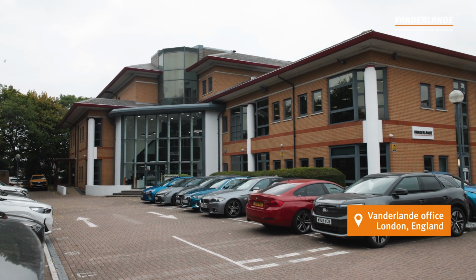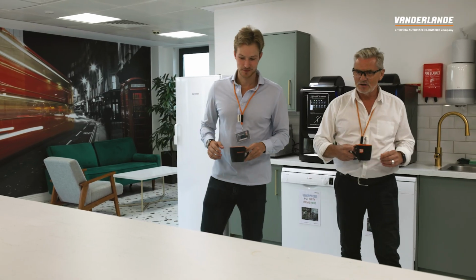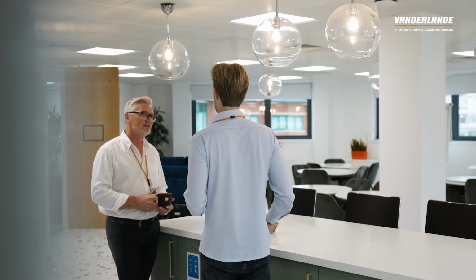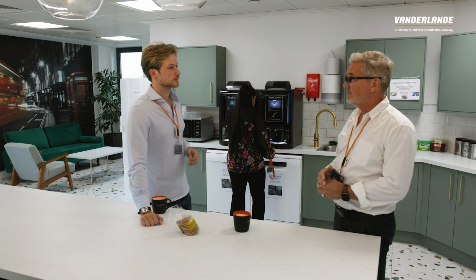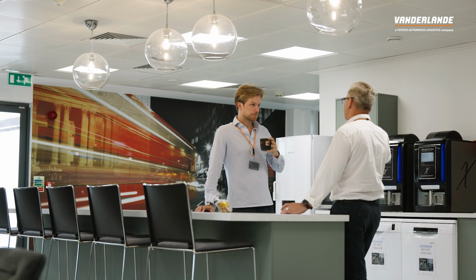Yeah, after all the online meetings, it's good to finally get you over here and show you around and show you what we've got. We have 2 terminals that have the IE5 drives now. How many do we have? So we've got 35 in Terminal 5 and 35 in Terminal 3 on the tub track systems. They've just finished being installed now and they're behaving really well. We've got some data loggers on them trying to get the data out for the energy saving.